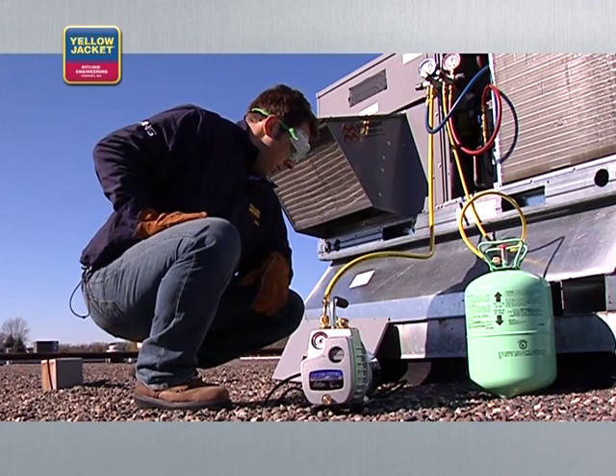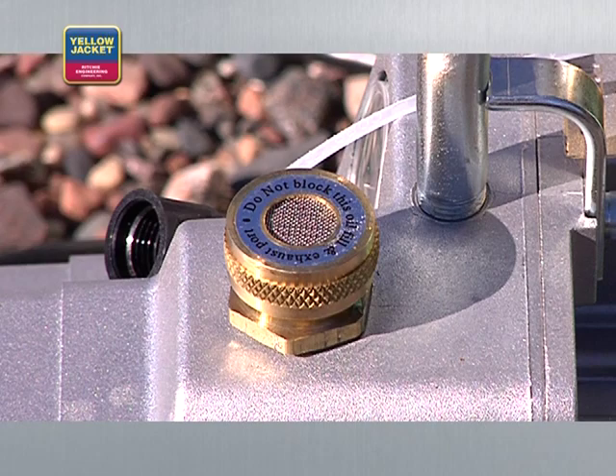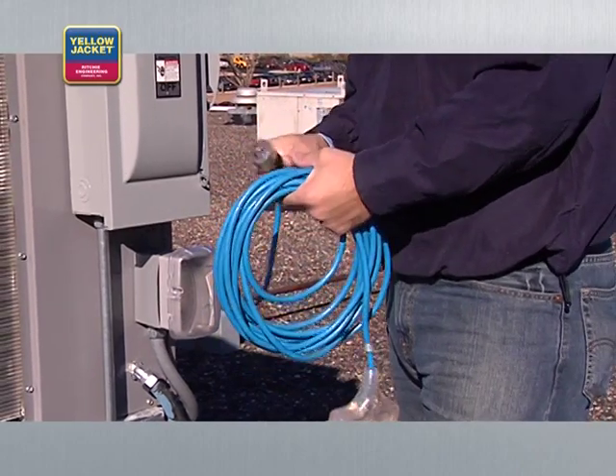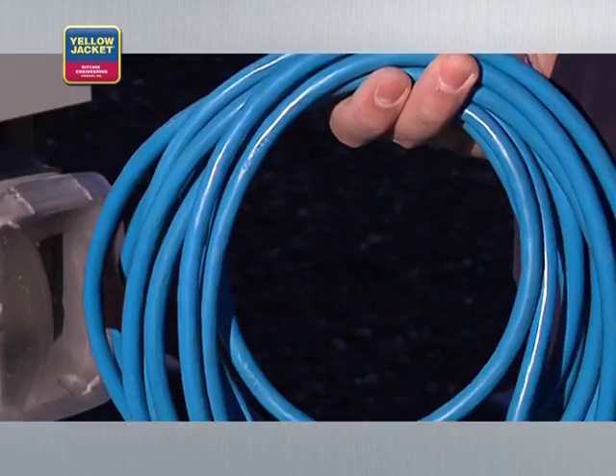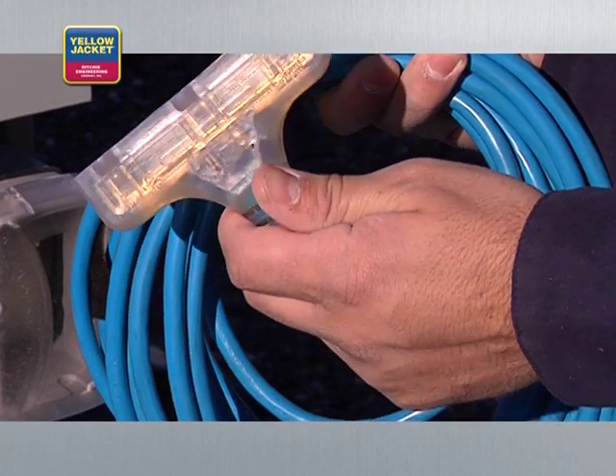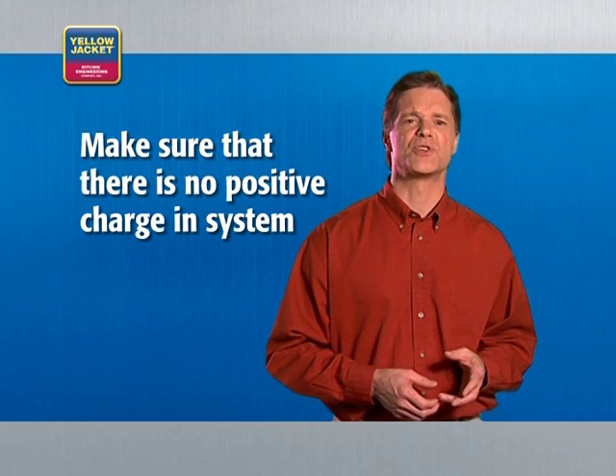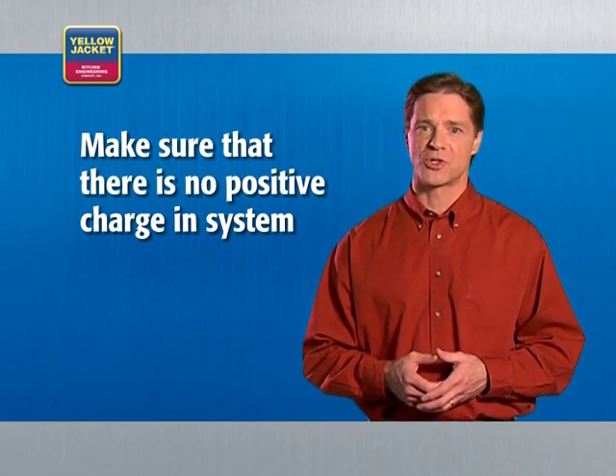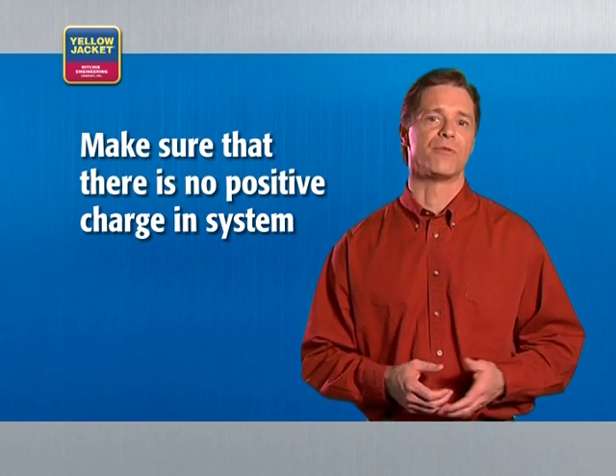Never block the exhaust port — make sure the area around it is free. Always use a grounded three-prong outlet and extension cord. Inspect electrical cords for damage before using them, and keep the cords dry throughout the process. Also, make sure that there is no positive charge in the system before you begin the vacuum process. Positive charge can damage the pump's vanes or valves.